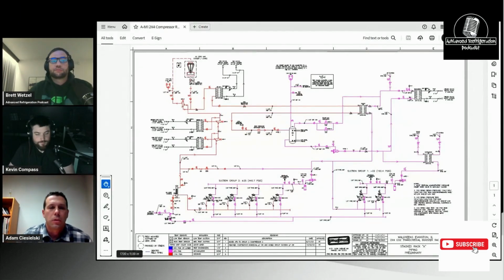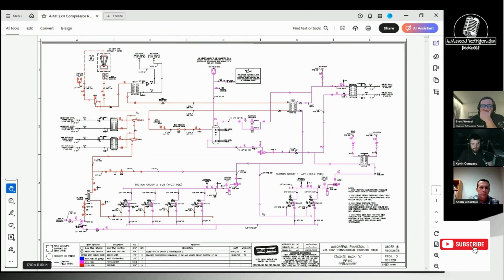Yep, absolutely. So just give me a little bit of background for the audience. This is a transcritical rack for a small grocery store, or not really a grocery store, but a pharmacy. So there's a couple small loads on this, a typical small freezer box and a typical small walk-in lineup of cases. But this rack is special because it's not just doing the refrigeration cooling for the walk-in box, the cooler and the freezer, but it's also doing all the HVAC cooling in the summertime, and then it's actually utilizing heat reclaim to warm the building as well. This is attached to a geothermal unit, so we are producing chilled water to provide the HVAC cooling.